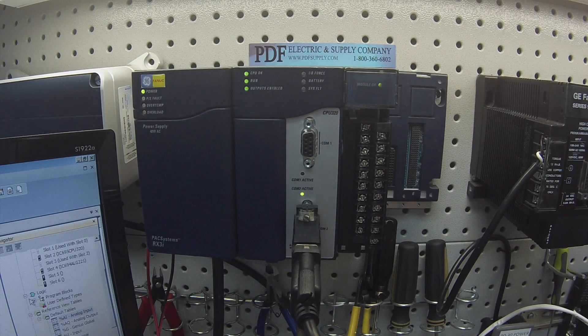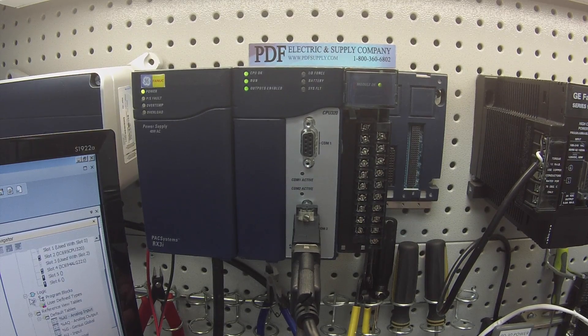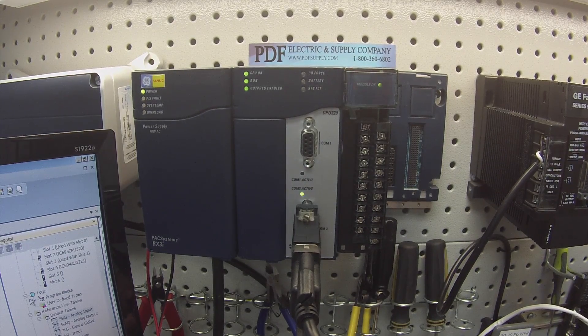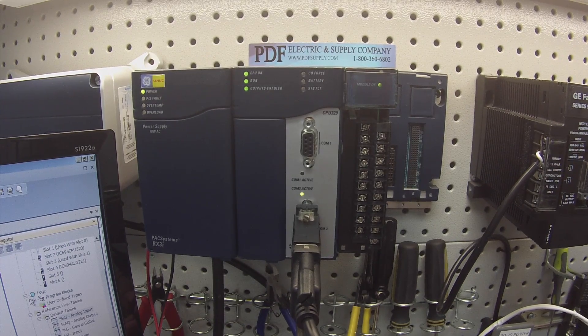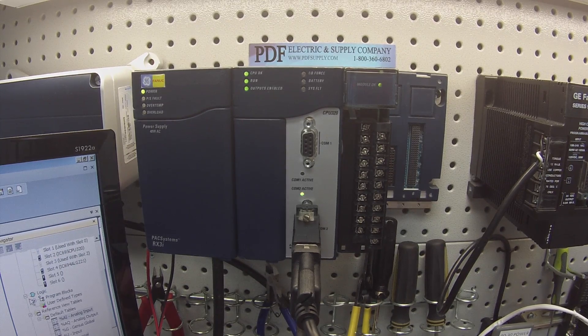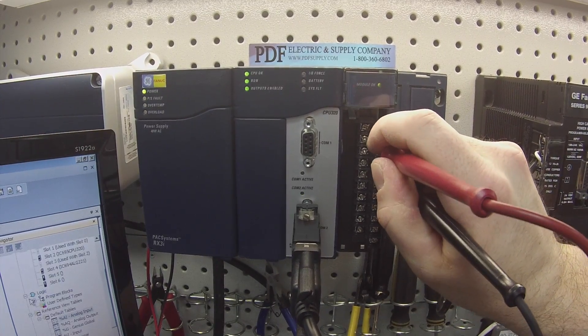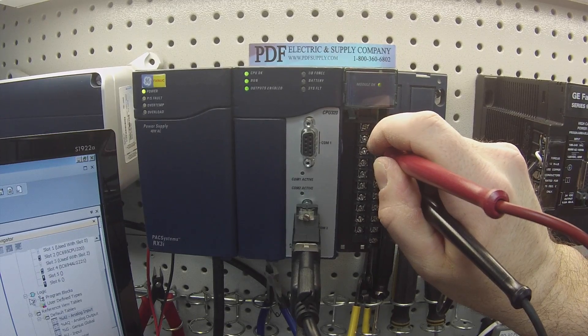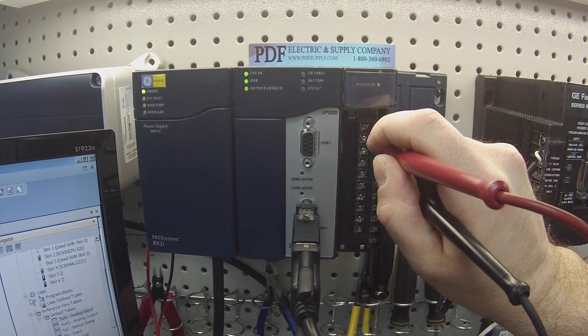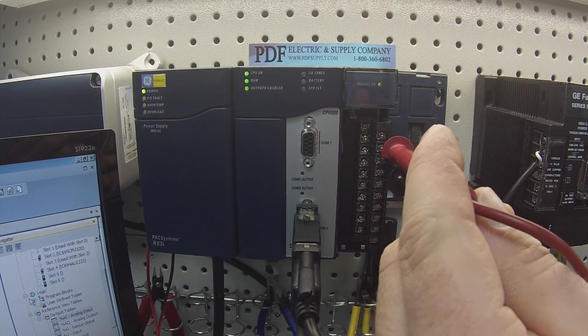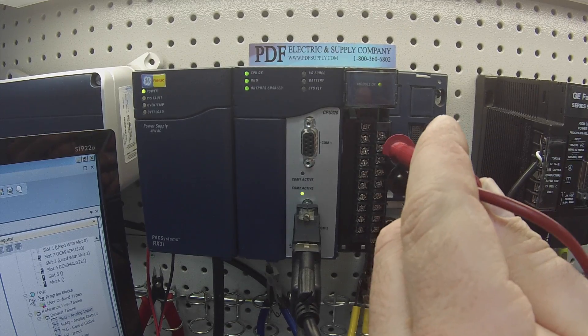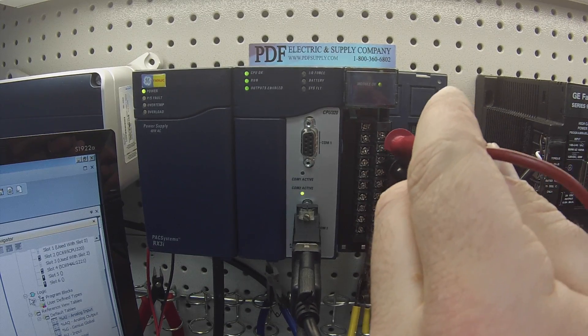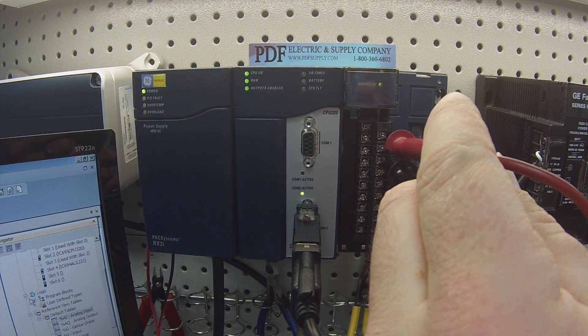The reason it's good to go up and down with the values is because what we typically see most often with a failed ALG221 or anything that measures current in milliamp, when the circuit does fail, it fails at full value. What that means is when I touch the probes to the channel, it will immediately go to 32,767. If you go up and down or attempt to go up and down on a failed circuit, it won't move. It will constantly stay at 32,767. That's a failed circuit.